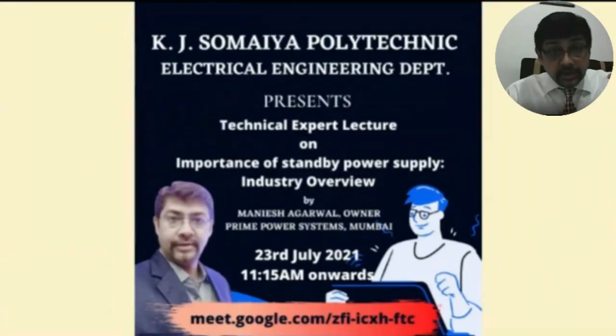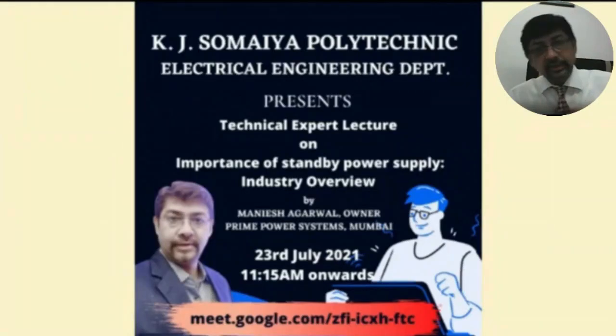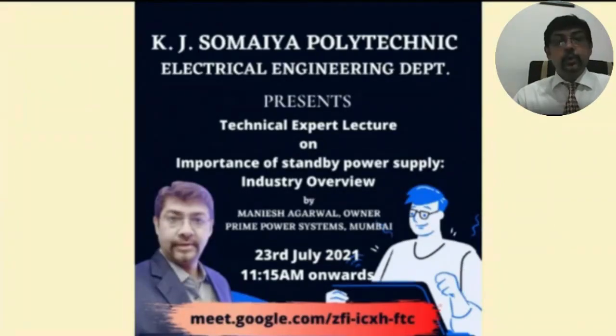But the generator requires around 20 to 25 seconds to come online. For those 20 to 25 seconds, that particular ventilator or ICU unit is on UPS, an uninterrupted power supply, but in a small capacity, maybe 5 kVA or 10 kVA, that's all. Otherwise, once the generator has taken over, the UPS will go offline and the generator will continue.